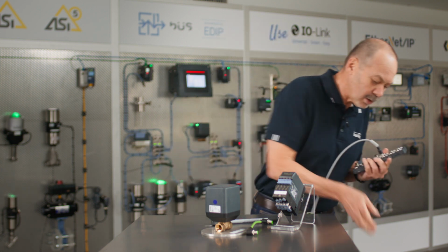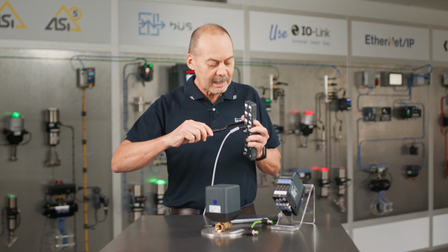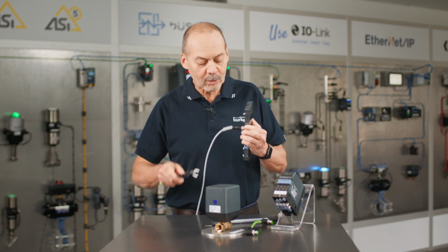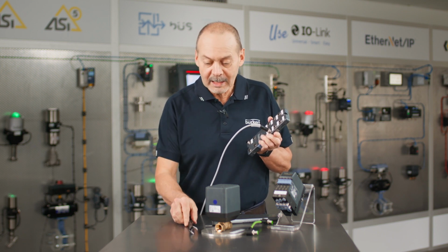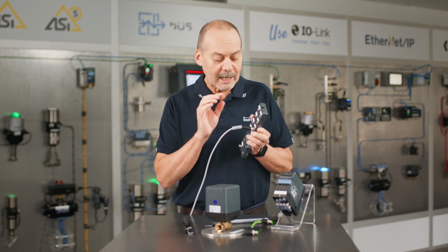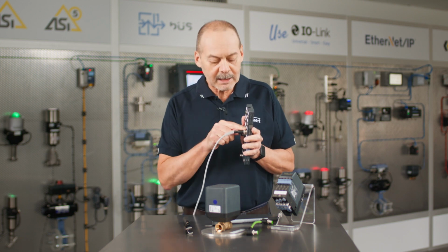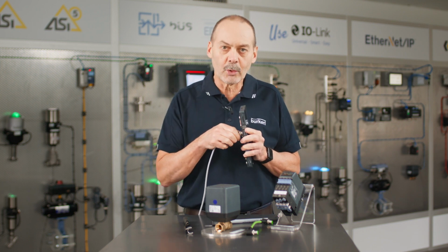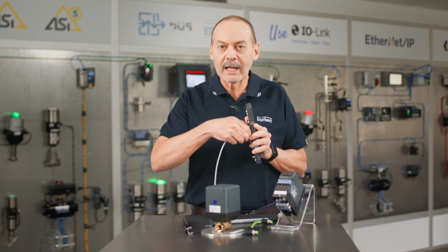What we suggest is to use a torque driver. So just to give you an idea, I've tightened that by hand, and now if I put that on there, I'm getting another good 3/4 of a turn, taking that to the recommended 1 Newton meter. Now I say 1 Newton meter, this is the maximum you should tighten it to, and we recommend that for metal to metal type connectors. If you're talking a metal to plastic connector or plastic to plastic connector, we would say maybe bring that down to 0.6. But even 0.6 or 1 Newton meter is still stronger than hand.